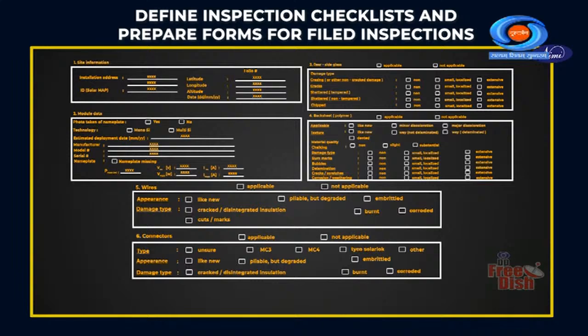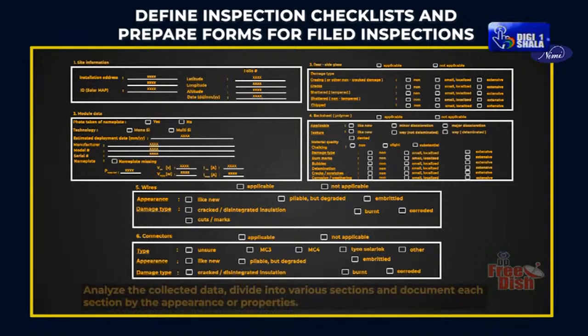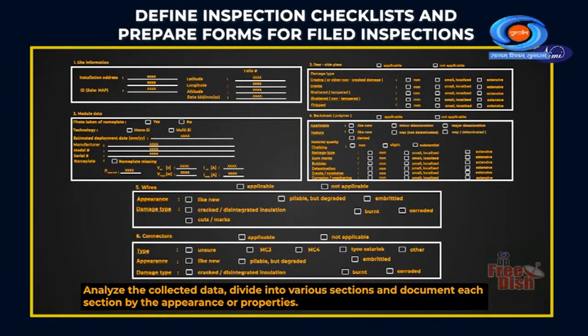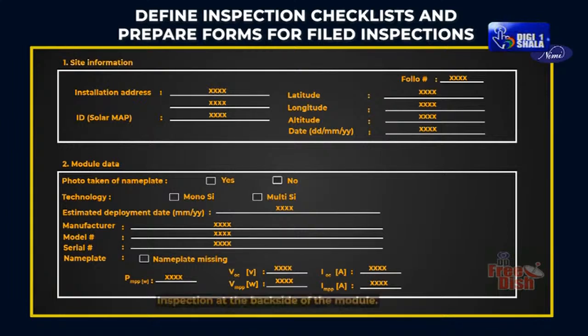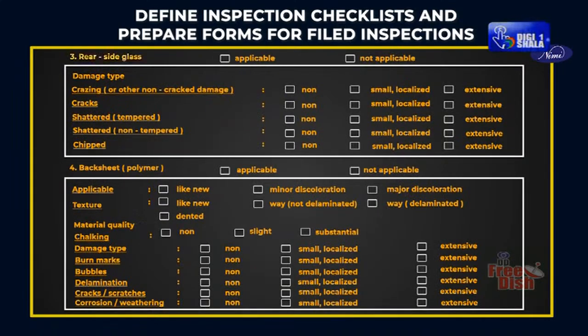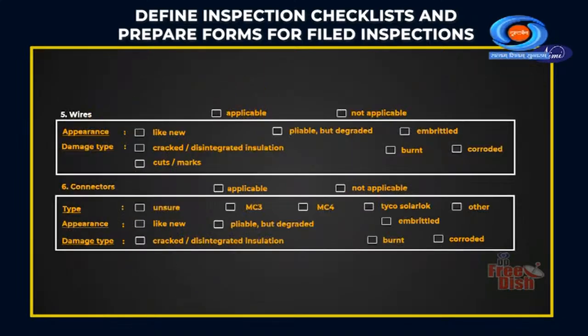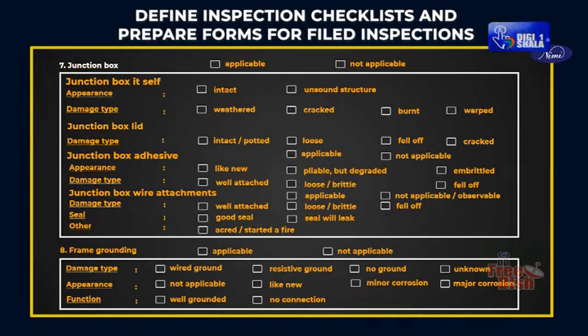Define inspection checklists and prepare forms for field inspections. Analyze the collected data, divide into various sections and document each section by the appearance or properties. Site information. Inspection at the back side of the module. Module data. Rear side glass. Back sheet polymer. Wires. Connectors. Junction box. Frame grounding.